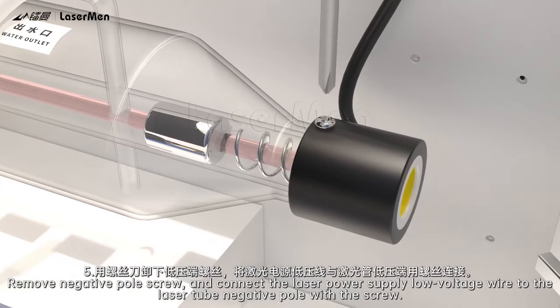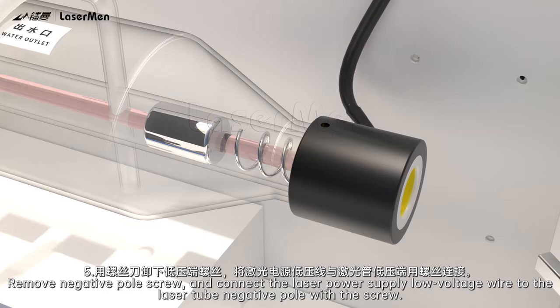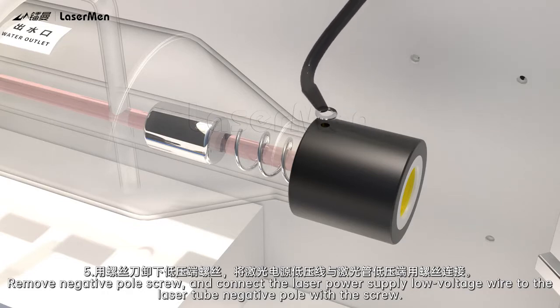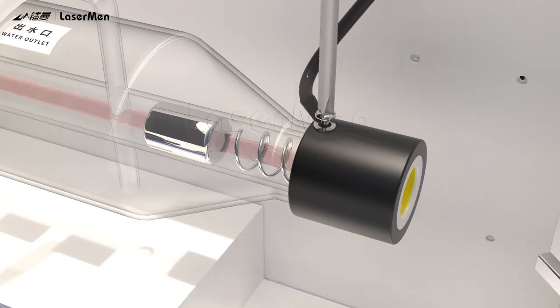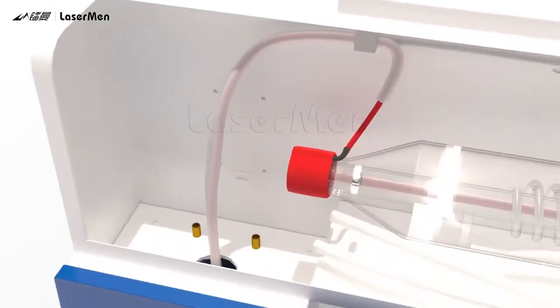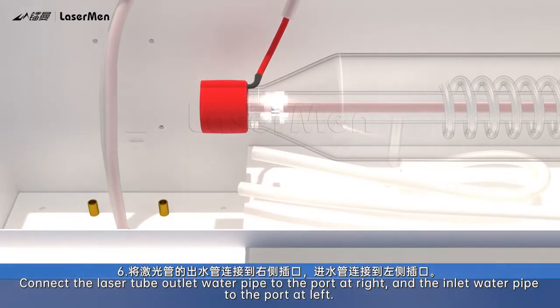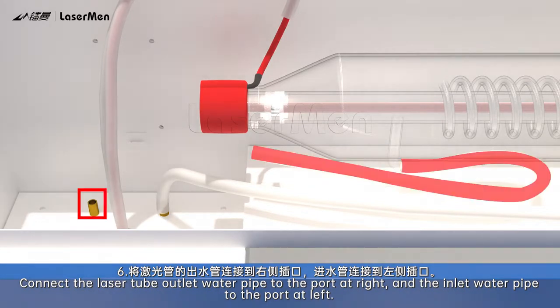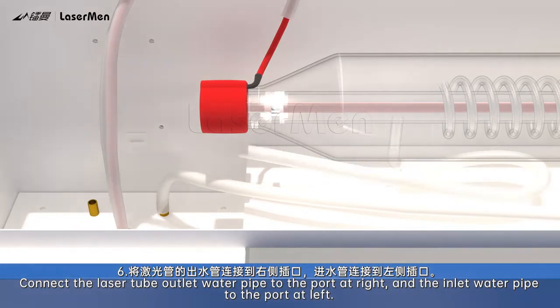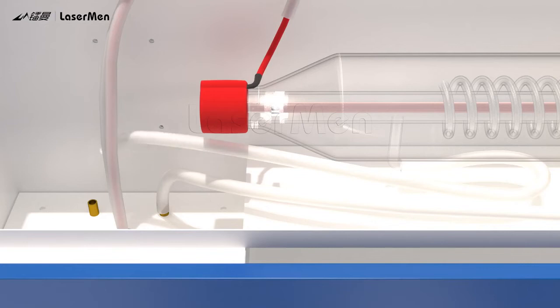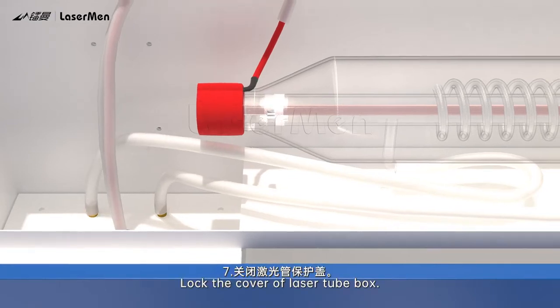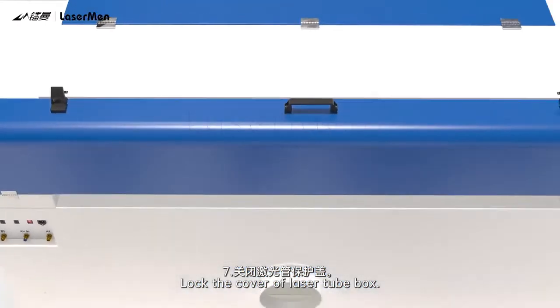5. Remove negative pole screw, and connect the laser power supply low voltage wire to the laser tube negative pole with a screw. 6. Connect the laser tube outlet water pipe to the port at right, and the inlet water pipe to the port at left. 7. Lock the cover of laser tube box.